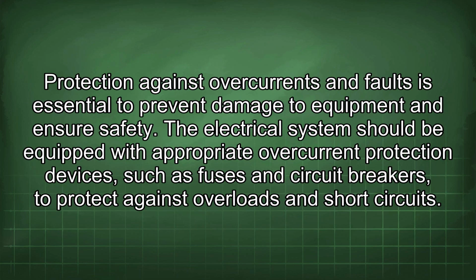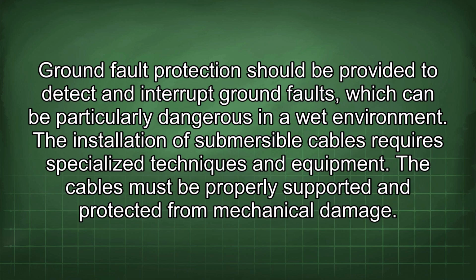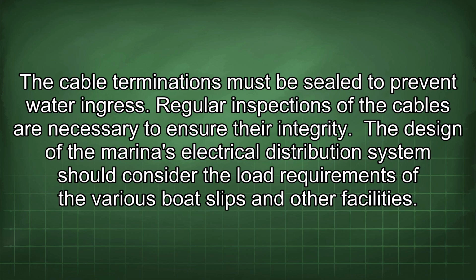Protection against overcurrents and faults is essential to prevent damage to equipment and ensure safety. The electrical system should be equipped with appropriate overcurrent protection devices such as fuses and circuit breakers to protect against overloads and short circuits. Ground fault protection should be provided to detect and interrupt ground faults, which can be particularly dangerous in a wet environment. The installation of submersible cables requires specialized techniques and equipment. The cables must be properly supported and protected from mechanical damage. The cable terminations must be sealed to prevent water ingress. Regular inspections of the cables are necessary to ensure their integrity.